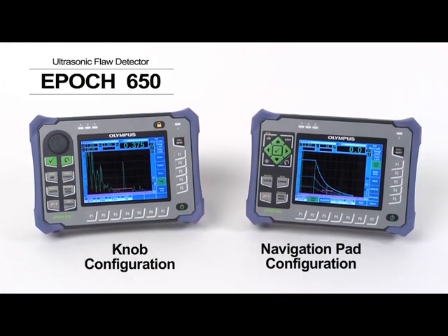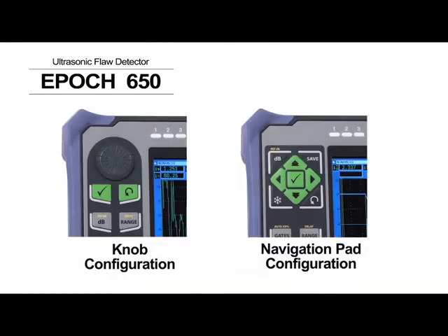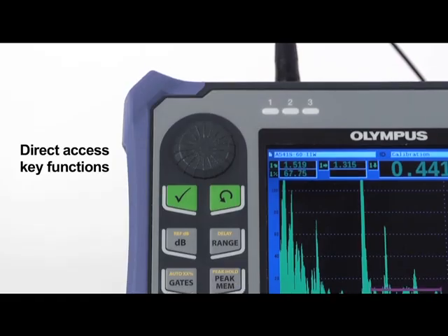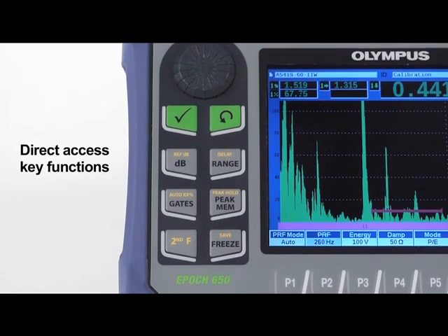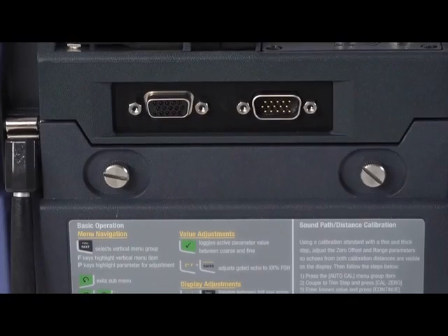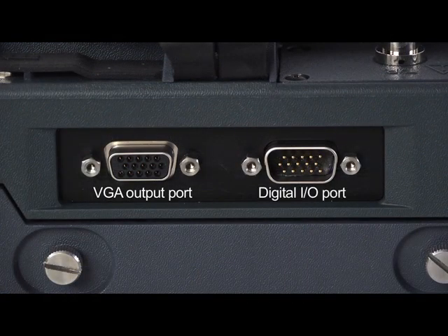The EPOCH 650 is available in either a knob or navigation pad configuration to meet the preferences of any user, and can be configured with BNC or large LEMO transducer connectors. Direct access key functions support immediate access to important inspection controls without the need for menu navigation. The instrument also features a standard VGA output port, as well as a digital I/O port for alarm output, serial communication, and trigger pulse synchronization.